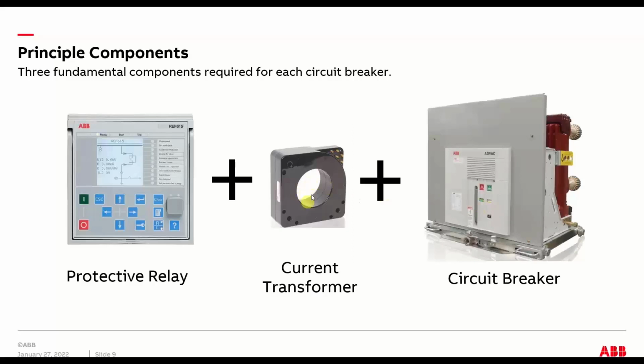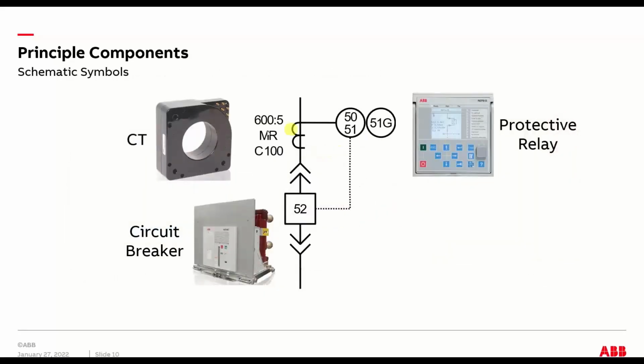Even the current transformer, people with a sharp eye will realize that this one here is a 600 volt class CT, but it's used in 15 kV switchgear because it goes around insulating bushings. So this is the actual class of CT that we would use in our medium voltage switchgear lineups. Here's a slide showing the physical device in relationship to some of the symbols used. So these two circles that show an instantaneous overcurrent and a time overcurrent ground, all these elements are part of this single box, plus a whole slew of additional stuff.